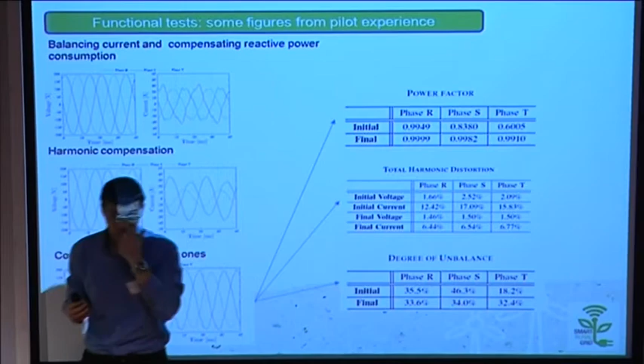In terms of harmonic distortion, the first situation before the connection of the IDPR is that we have, in terms of voltage, up to 2.5% of distortion, and in terms of current, about 17%. After the connection of the IDPR, we reduce the current distortion to 6.5%, and we have also corrected the voltage a little bit. This means an increase in the quality of service that we are supplying to the rural consumers.